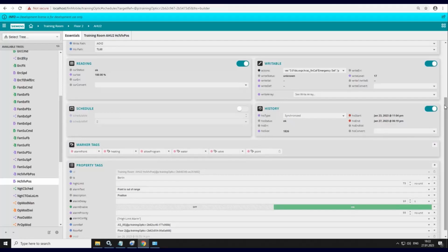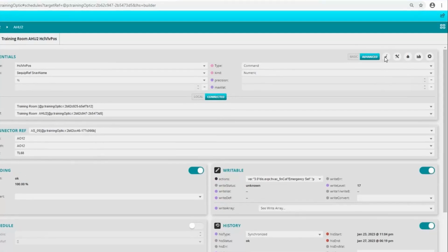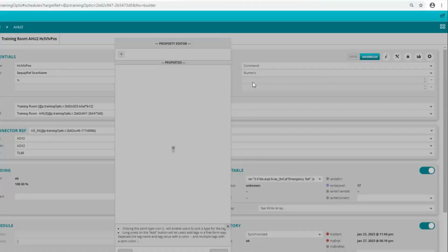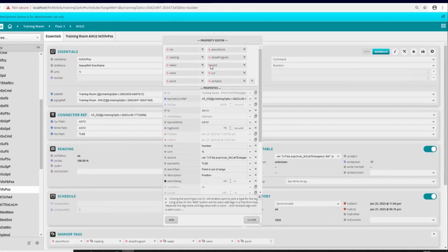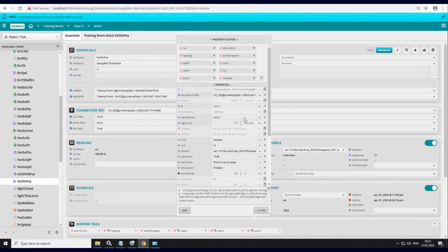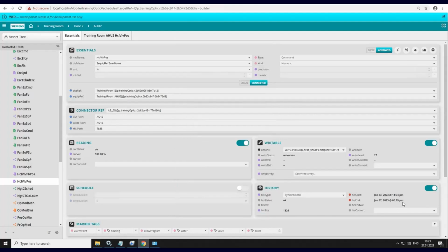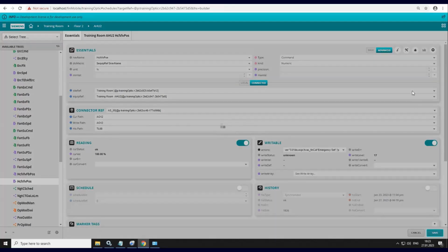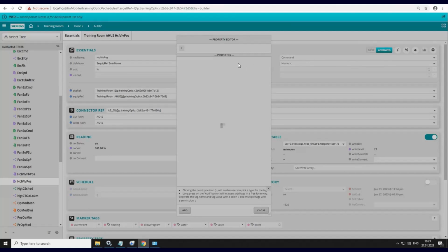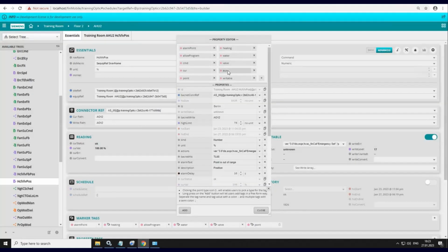Another part is that if I turn this trend off, you will notice something on the point. I'm going to show you, it's trended. We have our tags for our points up top. You don't see an AUX tag or anything like that, but when I turn the trend off, and I look at the tags up top, you'll see that the AUX tag comes in. If I turn a trend off for some reason or change that part of it, it's going to modify the point in the graphic based on the tags, and then it's going to need update binding.